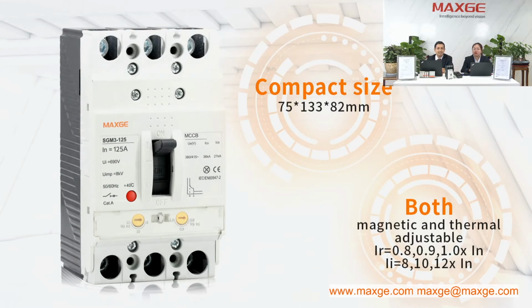For this SGM3-125, we have the compact size. Here you can see the size is very small, and it is also magnetic and thermal adjustable. The thermal adjustable range is from 0.8 to 1 In. Actually, we have 3 settings: 0.8, 0.9, and 1.0 times In. The magnetic adjustable ratings are again 3: 8 In, 10 In and 12 In. But we can also do customization as per customer requirements. Some customers may need 5 In to 10 In, and we can do that. So the spring on the magnetic side should be changed, as per the customer request.